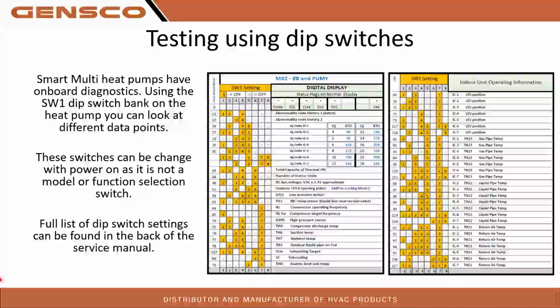Yep. So when you find something that needs to be corrected, you power off, wait for the lights to go out, and change your addressing. Now you can do one of two things. You can leave the power off for 30 minutes and your outdoor unit will forget what it saw. Or you can turn on SW2 switch number 2 and power it on for 2 minutes. When that 2 minutes is up, power it off, wait for the lights to go out, and then turn off 2-2.